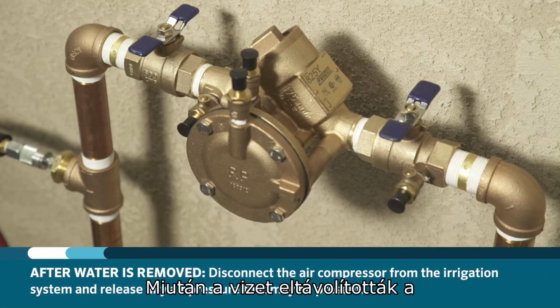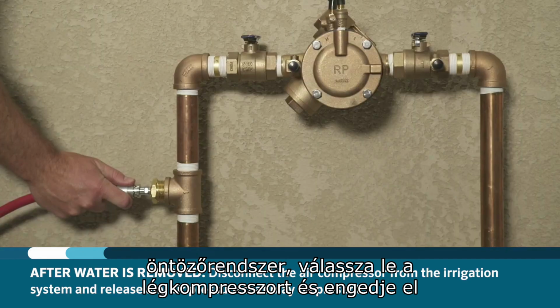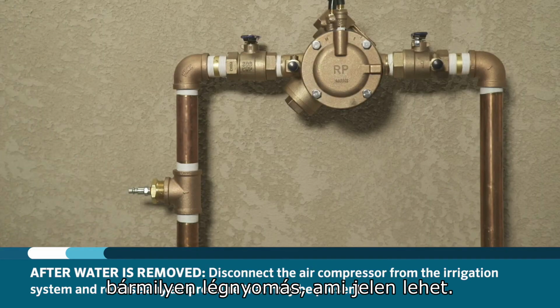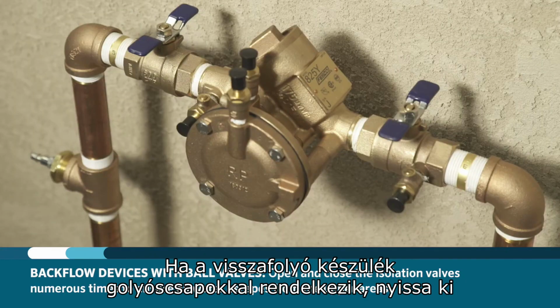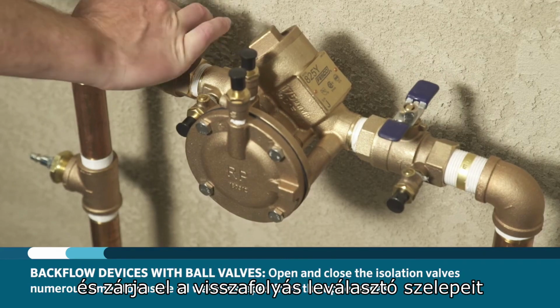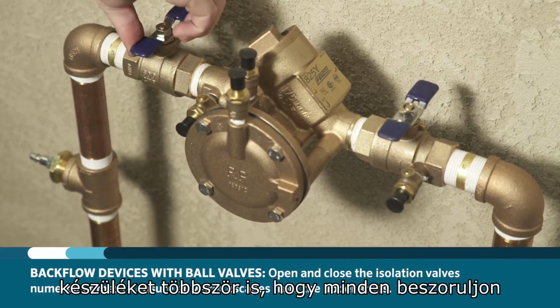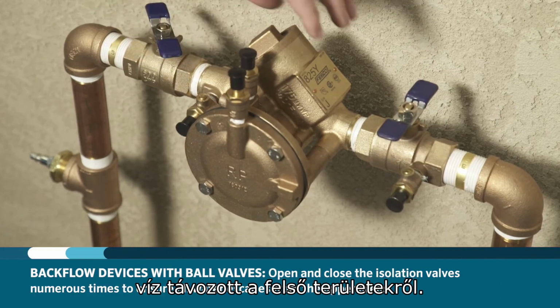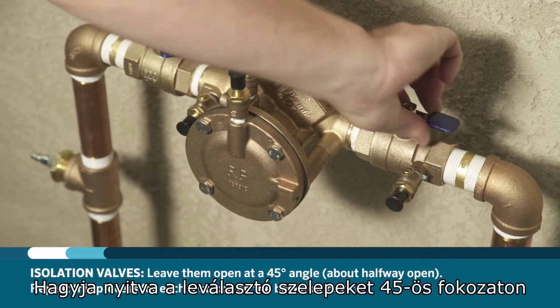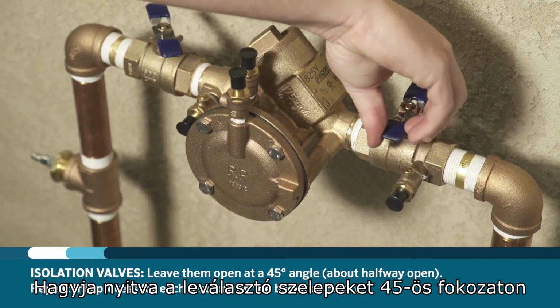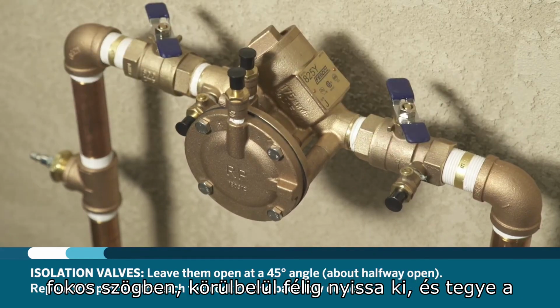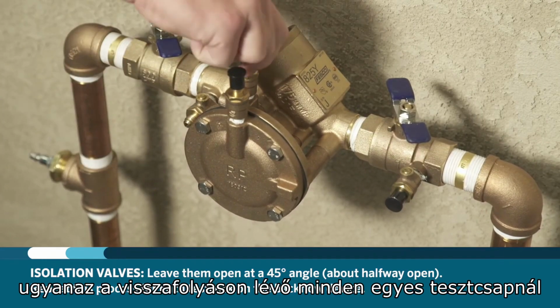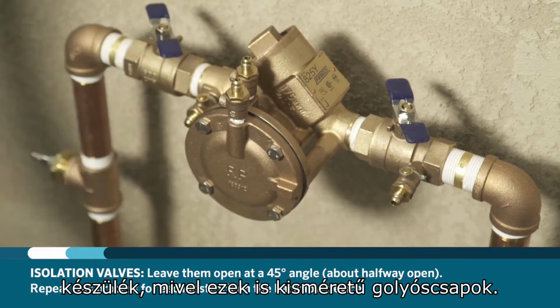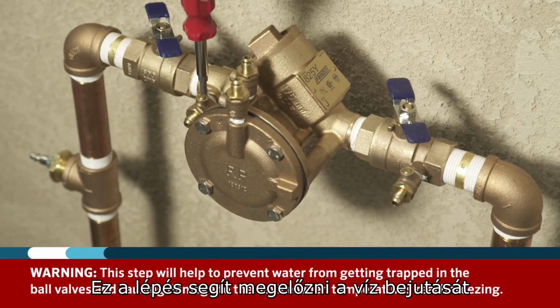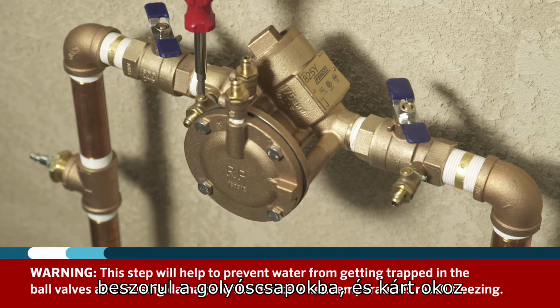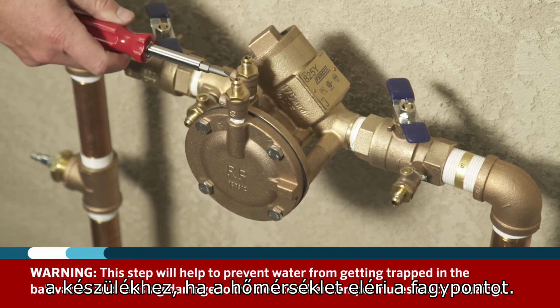Once the water has been removed from the irrigation system, disconnect the air compressor and release any air pressure that may be present. If your backflow device has ball valves, open and close the isolation valves on the backflow device numerous times to ensure that any trapped water has escaped from the upper areas. Leave the isolation valves open at a 45-degree angle, approximately half open, and do the same for each test cock on the backflow device, as these are also small ball valves. This step will help prevent water from getting trapped in the ball valves and causing damage to the device when the temperatures reach freezing.